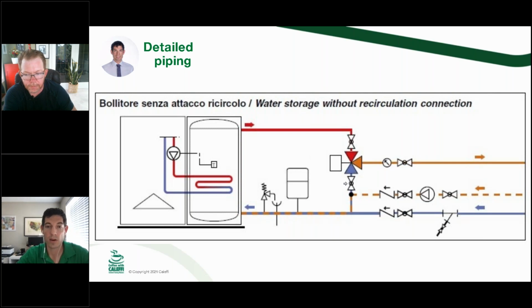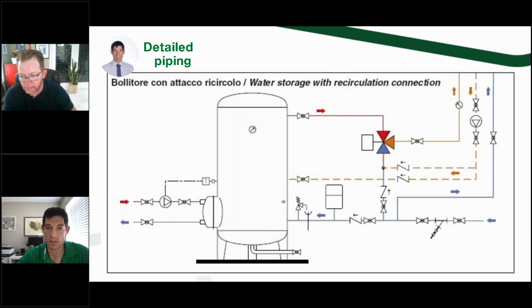So one of the things that Michael and I were talking about before is that the price of the Legio mix, even a smaller one, an electronic mixing valve, is going to be more expensive than a non-electronic thermostatic mixing valve. However, to install it to prevent the recirc creep, piping there are more steps involved. And then you need to have the globe valves. Back one slide. You have to have the globe valves to balance that. So there are additional components in play here, and it's a little bit more work. So if you look at the full installed cost of the Legio mix versus the thermostatic, it can make more sense to just go with a valve that's going to protect from that recirc creep, regardless of how you pipe it with either of the two diagrams that we give you.